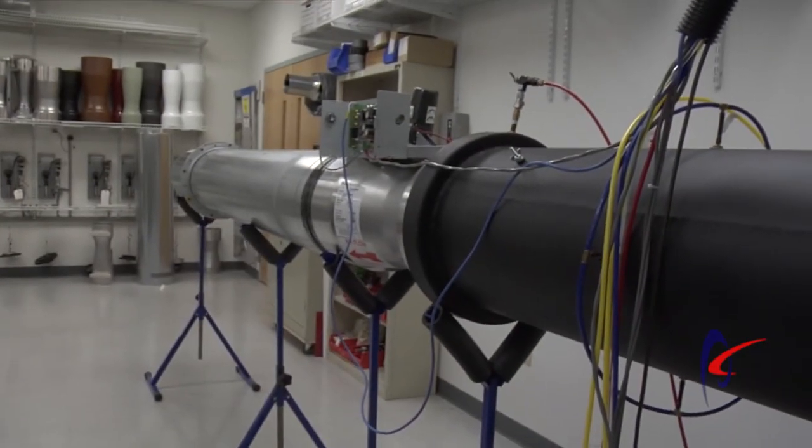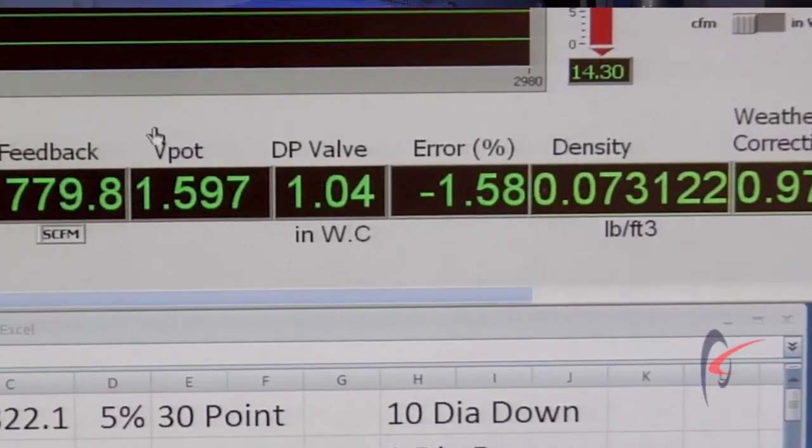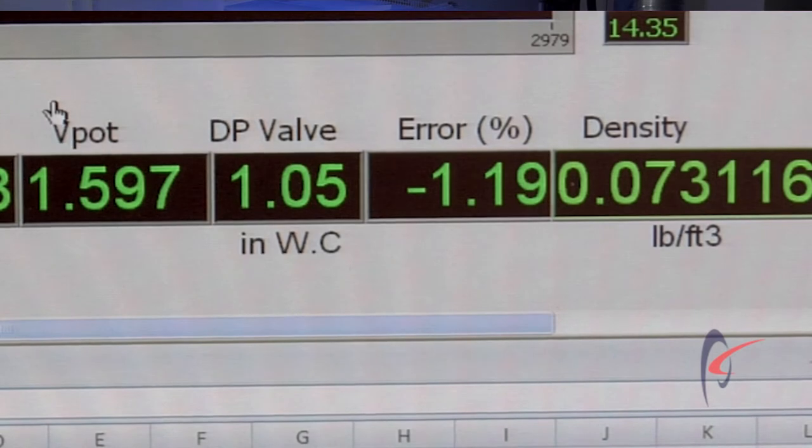The feedback from the valve gave us a result that was within two percent of the NIST certified airflow station.